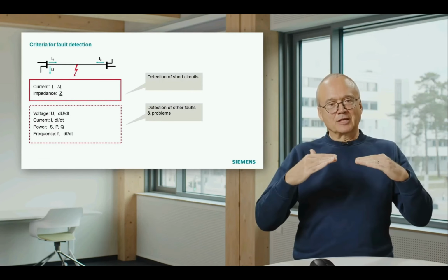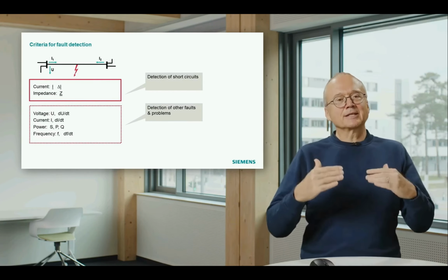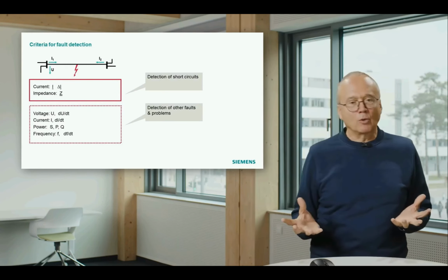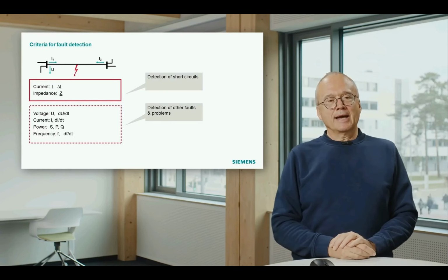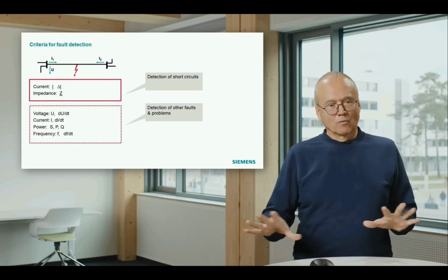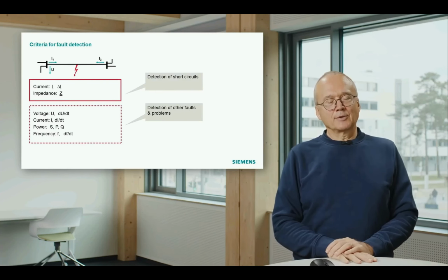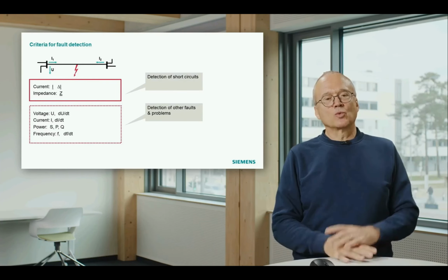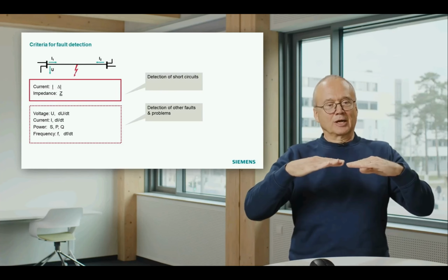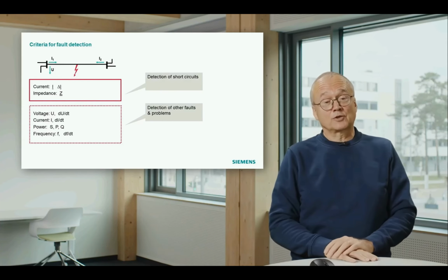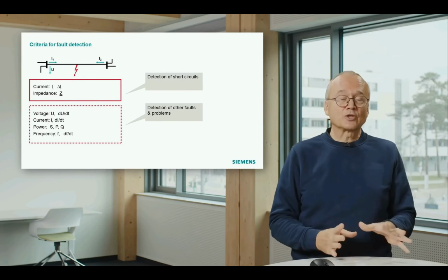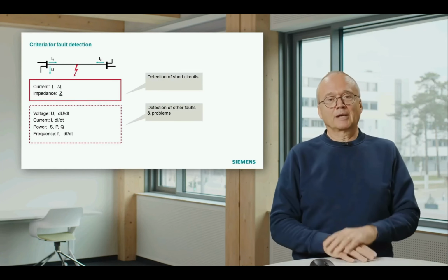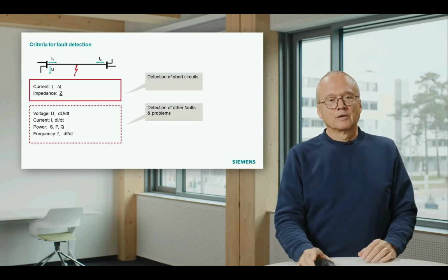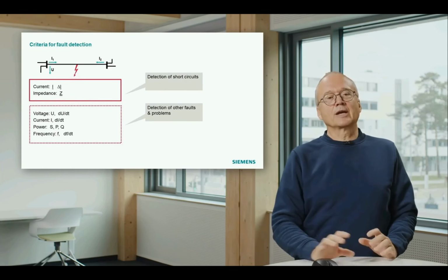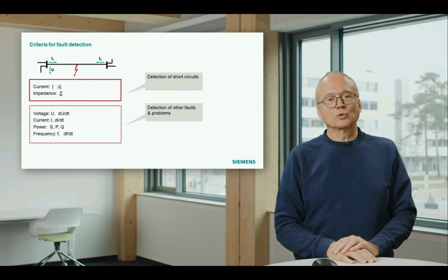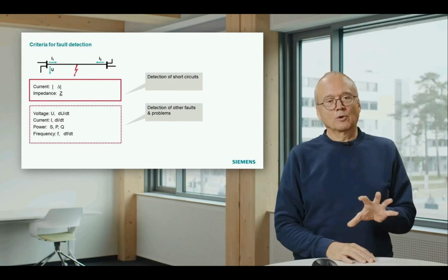And if the frequency goes down, it's an indication that there's a lack of power in the system. And so what we often have in the systems is that if we see the frequency goes down, or we have a certain rate of change of frequency, we disconnect loads to stabilize the system. So these criteria here on the bottom are used to detect other faults.